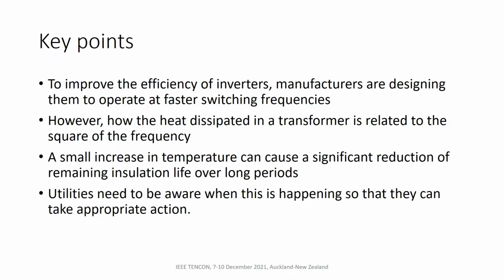Now, we started to get concerned about this in terms of what's happening in the transformer, because the heat being dissipated within the transformer is highly inductive. It's actually related to the square of the frequency of the harmonic. So if we have fairly low-order harmonics going into our transformer, and then we have higher harmonic frequencies, we might find the heat dissipated is higher with the higher frequencies. It's not only a function of the current.